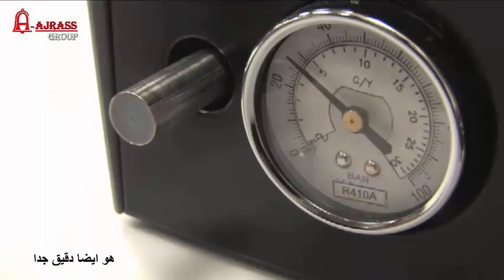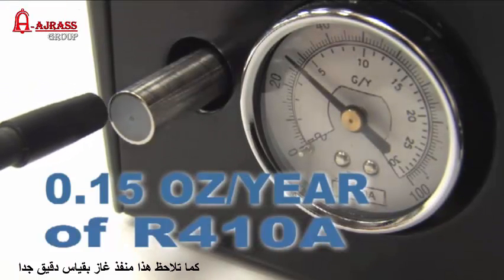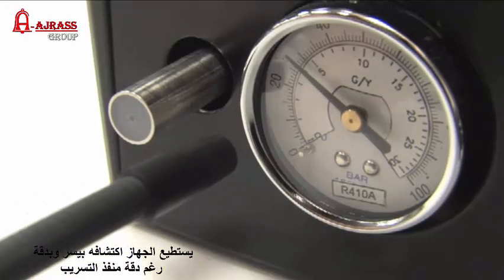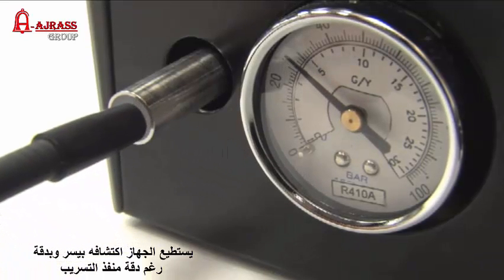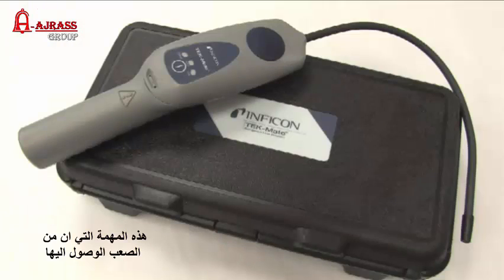It's also very sensitive. This is a 0.15 ounce per year leak of R410A, and TEK-Mate detects it immediately. This leak size is even smaller than the minimum guaranteed sensitivity of a quarter ounce per year — it's the kind of sensitivity you can expect from TEK-Mate on the job site.